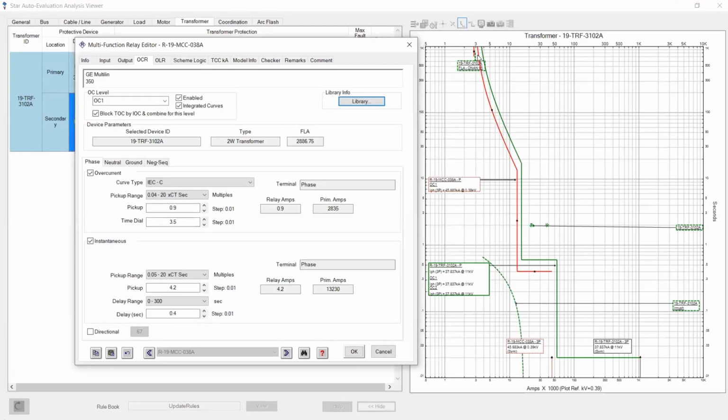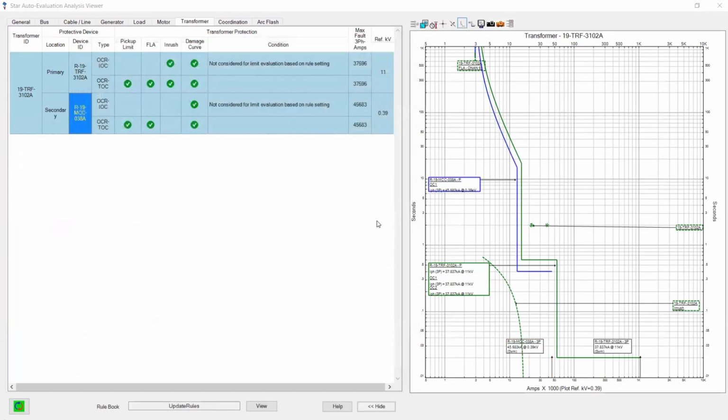It's very complex to notice here in the chart, but by benefit of the protection Star Auto-Evaluation, you can very quickly and rapidly control and verify everything. So for the transformer, this type of mistake may happen very infrequently, but for motors, you may update a little bit of data, efficiency, power factor, and so on.